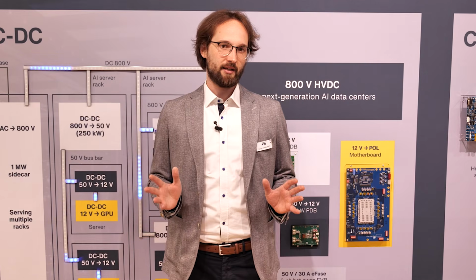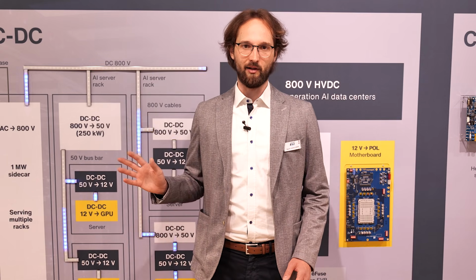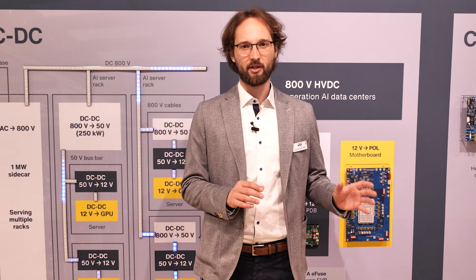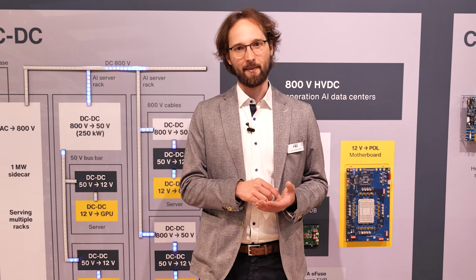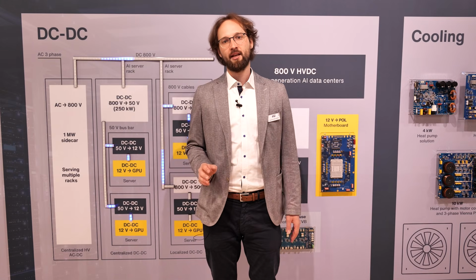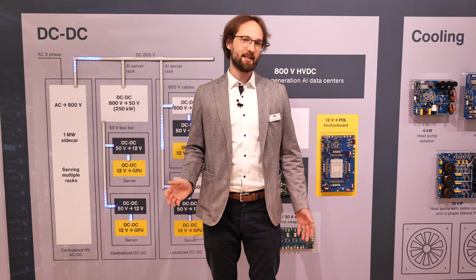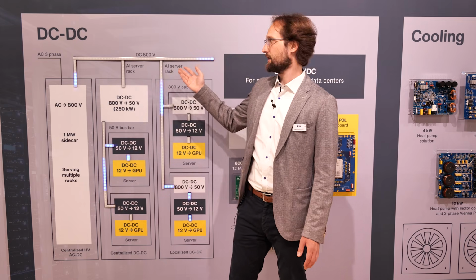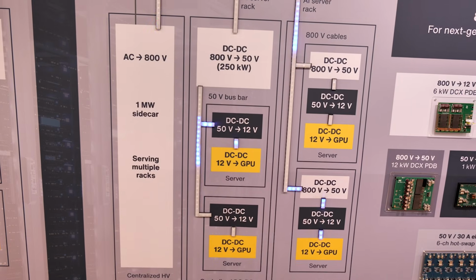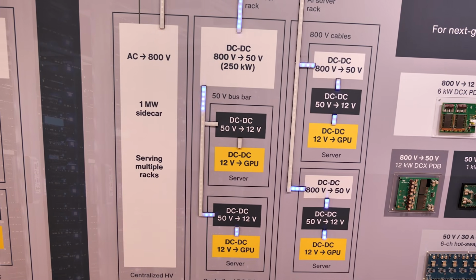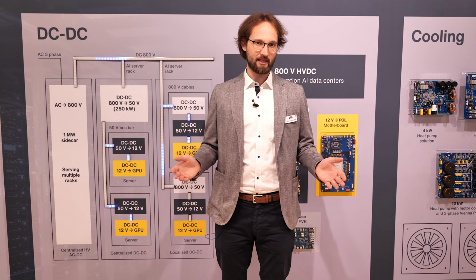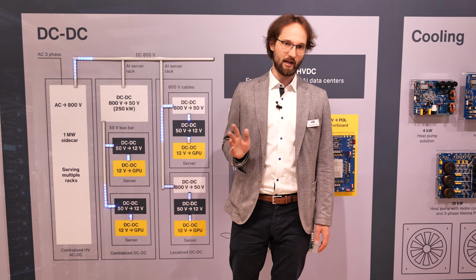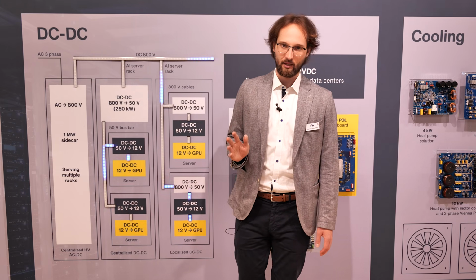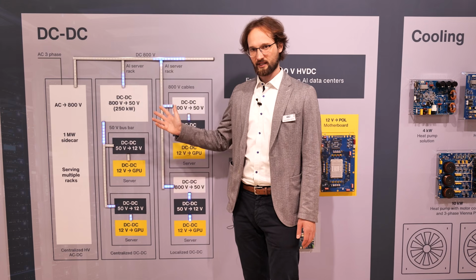This is the 800-volt HVDC story. The arithmetic is simple. At 50 volts, delivering 1 megawatt means 20,000 amps. With current that high, conductive losses become excessive. At 800 volts, the same 1 megawatt is just over 1,000 amps. Simple Ohm's law, saving a lot of copper wiring. Three architectures are presented here.